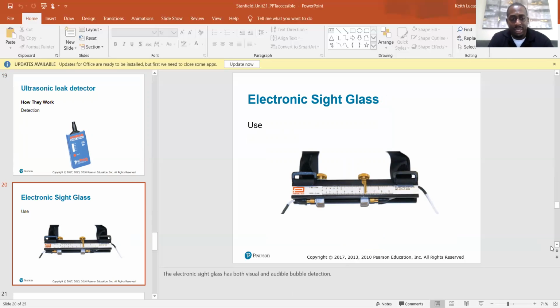Electronic sight glass. The electronic sight glass has both visual and audible bubble detection. Now that's one that I've never used, and I think I'm going to get it, because it's a pretty cool tool. It's got these two little sensors that you put on the liquid line in various areas, and it'll let you know if there are bubbles in your liquid line coming out of the condenser or before or after your filter dryer, to let you know different things.